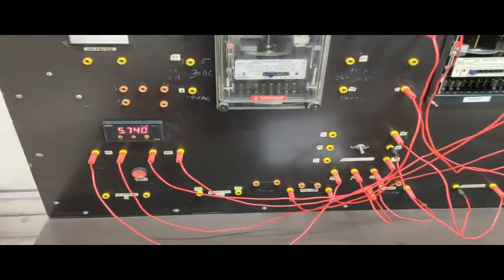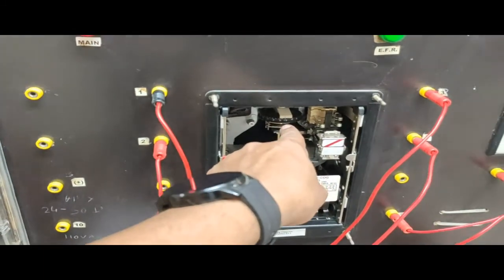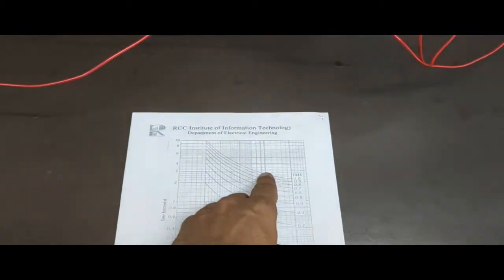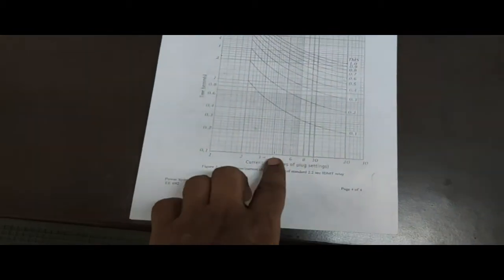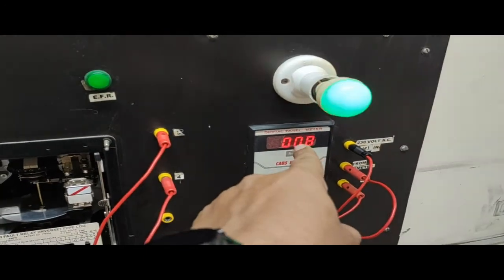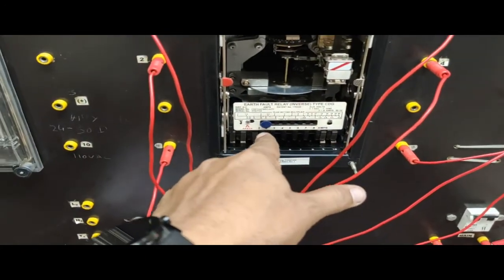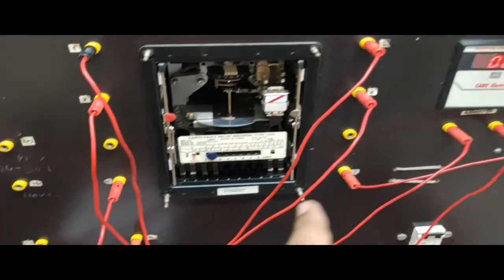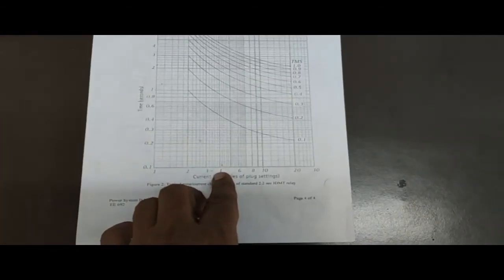5.740 seconds is required to operate the relay. So that means as the time setting multiplier is fixed at 1.0, the same curve will be taken, and now the 0.8 will be the relay coil current and 0.2 is the relay plug setting. So the plug setting multiplier will be 0.8 by 0.2, so that means 4. So now you have to find out the 4.